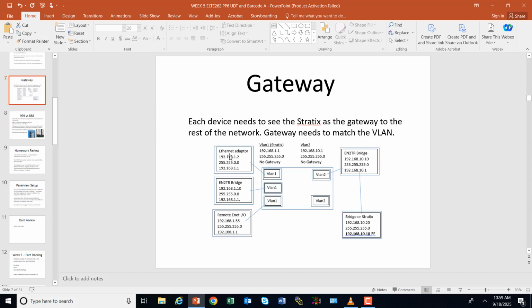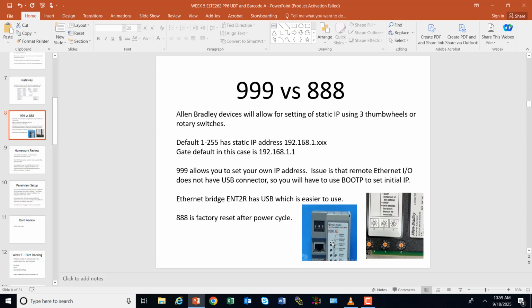Now, that's where I was trying to tell you that when you do this managed switch, if you make this managed switch a .1, that's good, because then it's going to see the gateway as the managed switch, and boom, this remote Ethernet is going to work right away because it gets defaulted to 1. If for some reason you wanted to make it a different, like a 172 network, you could set this to 999, and then set the IP address of it.